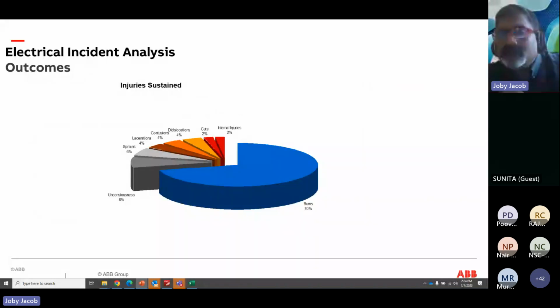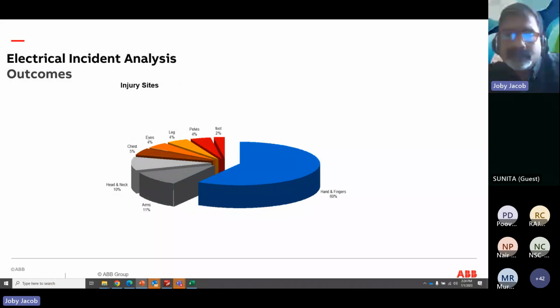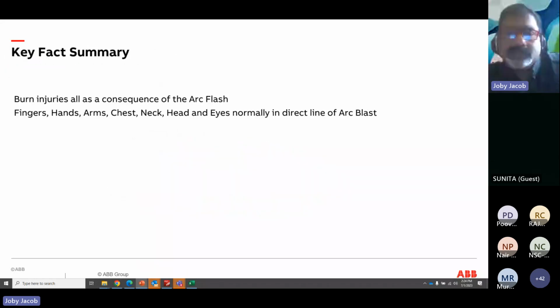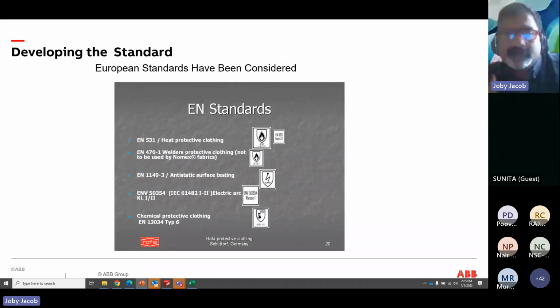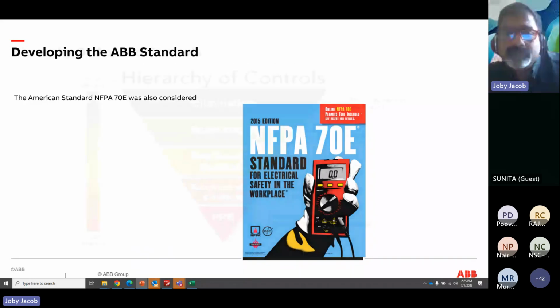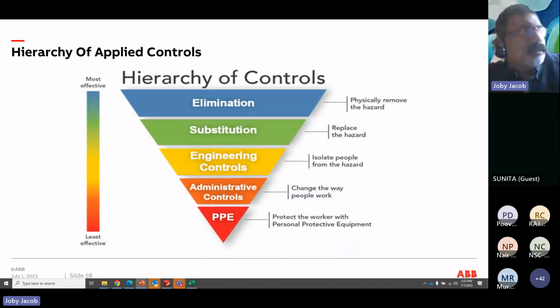Outcomes: this is more related to our own incidents. Mostly we find that burn injuries are the predominant ones. 70% comes from burn injuries, and hands and fingers are mostly exposed. And we try to include the standards inside ABB. We try to adopt the NFPA standards for the clothing part also. Again, the hierarchy of controls is adopted: how we can eliminate such arc flash risks, what the substitution is, how you replace the hazard, some engineering controls which we already discussed, and administrative controls. And the last resort is PPE.